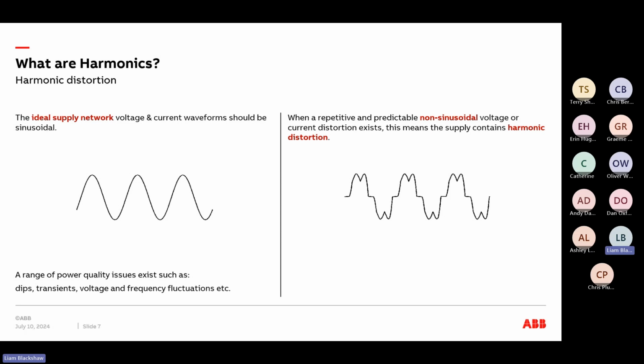This is probably slightly over-exaggerated, just to give you a bit of a feel and an appreciation of what harmonics look like. But that's what a typical waveform would look like when you have a repetitive and predictable, non-sinusoidal voltage or current existing in your supply system. It means that the supply contains harmonic distortion.